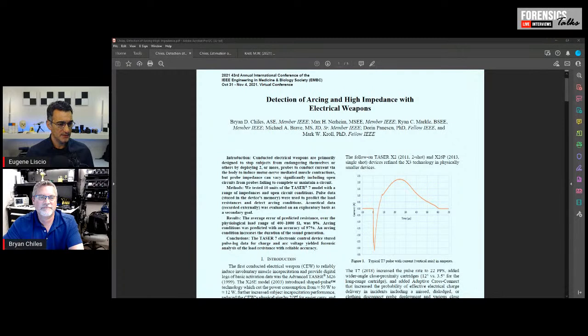So yeah, with probe analysis, the probes are attached to a wire, but the wire is not welded to the metal—it's just a knot tied in there on the old probes. The newer probes, it's crimped on there, but there's a gap there. So when the probe is connected to the body and conducting, the electricity has to pass from the wire to the metal on the probe. That leaves a signature that can be looked at. For instance, with the scanning electron microscope, you can look really closely at the metal and see the signature of how many pulses actually went to the probe.